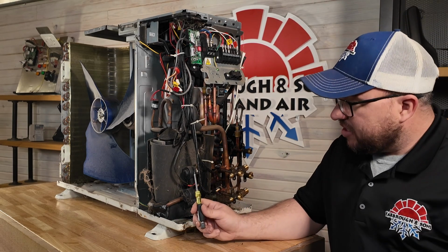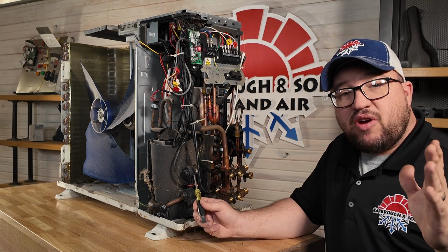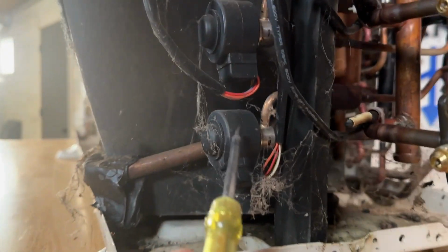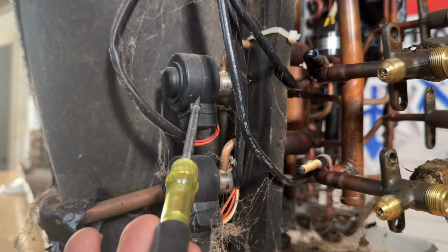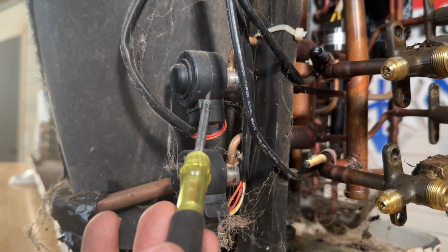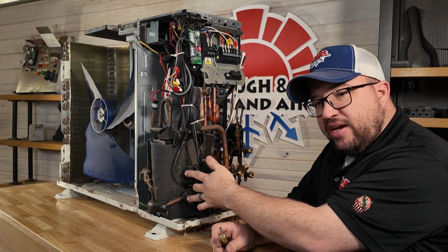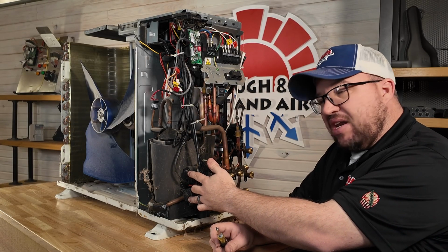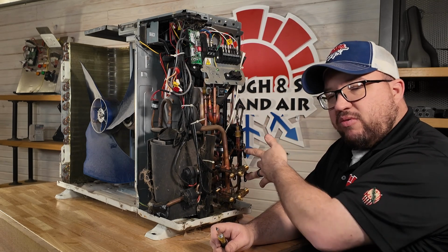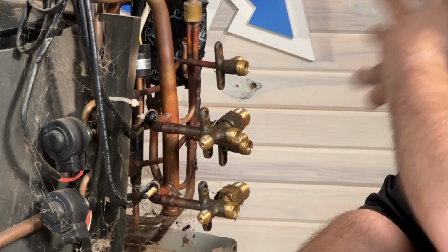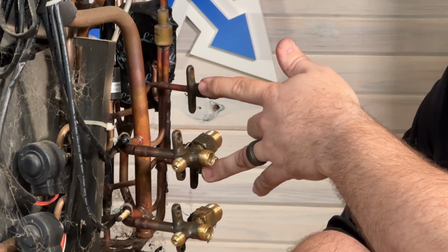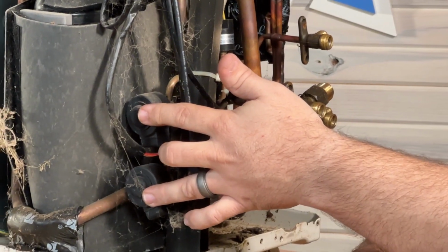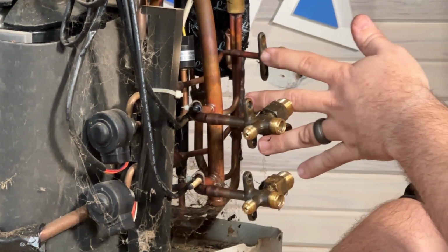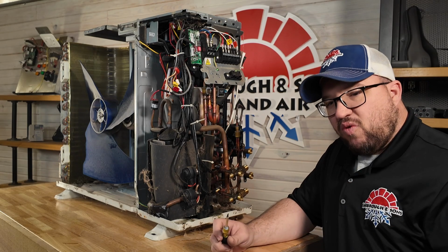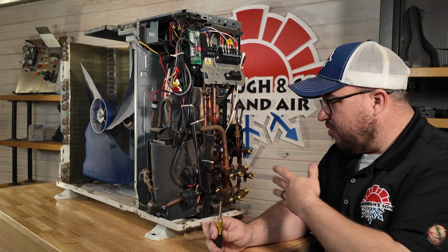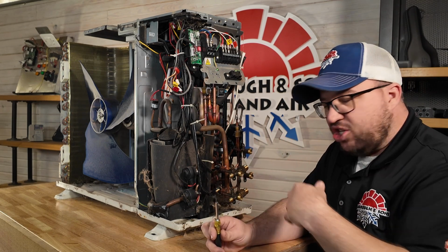Some other things on here are your EEVs. So this is your actual metering device. As you see on this one, we have 2. Now, what's different from your normal system is that your actual metering devices are on the outside. So one thing you'll definitely see on mini splits is your liquid line is actually covered in insulation. That's because it has the potential to sweat, because the actual metering of that refrigerant is done out here instead of inside. So we want to make sure we protect that so it's not sweating if it's in your walls, in your attic, going through anything like that. We want to make sure you're protected there, so it should be insulated.